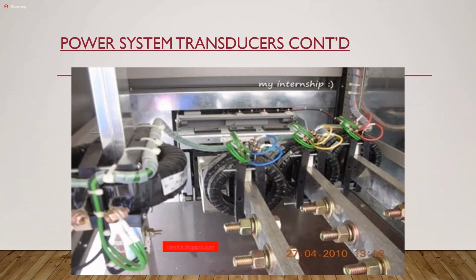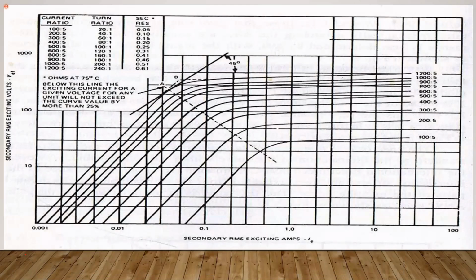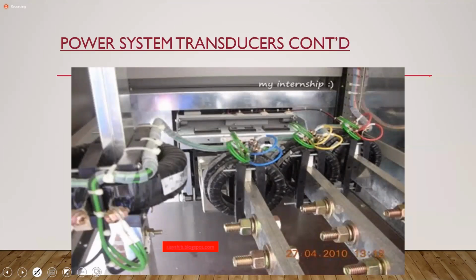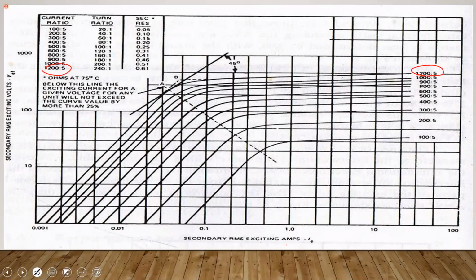So it's a, let me see, let's just go to that. So it's a 1200 to 5 CT. What that means is that on the outermost winding, which is there, if we have 1200 amperes on the primary of the CT, or in other words, if we have 1200 amperes on the bus bar, so if 1200 amperes is being taken, then on the output of the CT you'd see 5 amperes. So in other words, if you then have 2400 amperes on the primary, then you'll see 10 amperes on the secondary, and so on. Any questions?